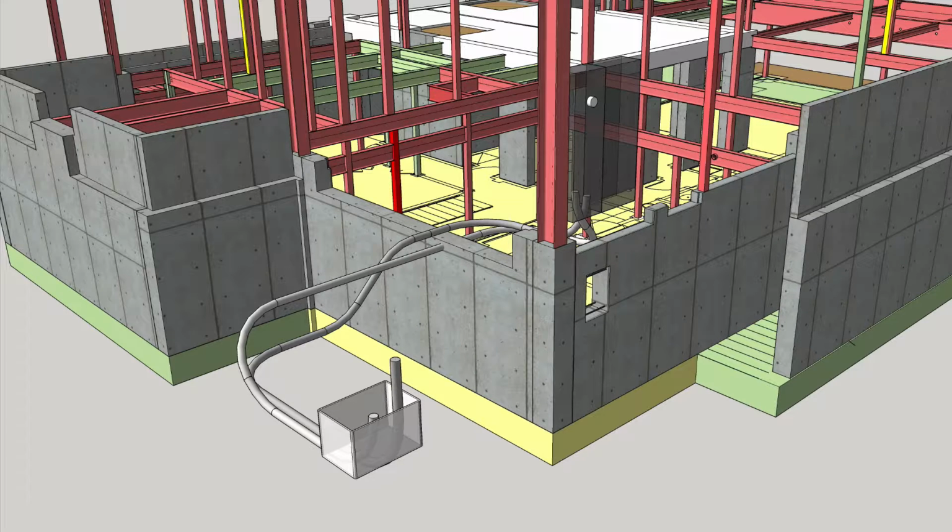With this next iteration, we're still looking to maintain a close path and short distance between the handhole and service panel, but as you can see, this configuration resulted in more than 270 degrees of sweep between 2 points, and would not satisfy the utility requirements.